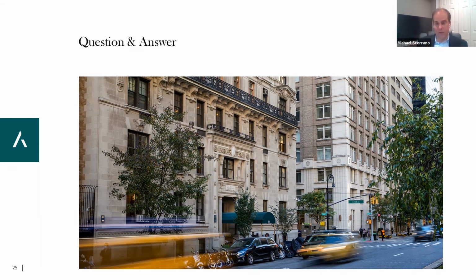So what we find as a viable measure is to put in a cogen system along with a hot water absorption chiller, then recover whatever heat we can in the summertime and use that for cooling. I have a building I'm working on now that put in two microturbines a couple of years ago and didn't have a good use for the waste heat in summer. We're putting in a hot water absorption chiller to recover that excess waste heat they were basically dumping, and use it to make 50 tons of air conditioning. That was definitely a good way to do it.